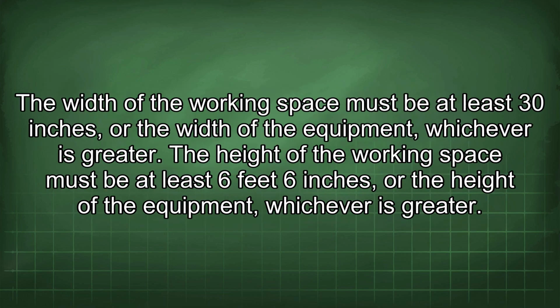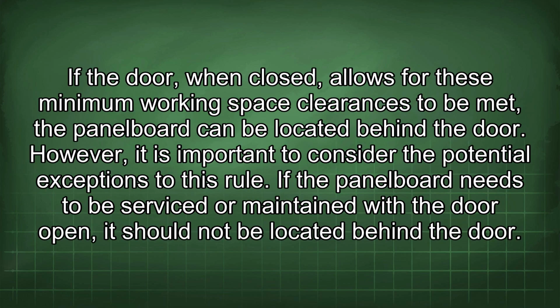The width of the working space must be at least 30 inches, or the width of the equipment, whichever is greater. The height of the working space must be at least 6 feet 6 inches, or the height of the equipment, whichever is greater. If the door, when closed, allows for these minimum working space clearances to be met, the panel board can be located behind the door. However, it is important to consider the potential exceptions to this rule.